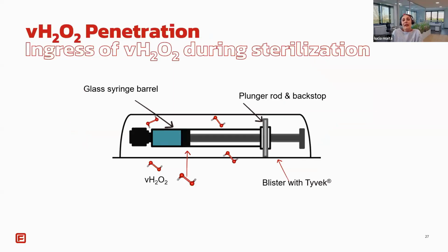This slide focuses on the key aspect of the H2O2 process: the sterilant penetration. The aim is to verify that H2O2 can effectively reach all the critical areas of the system, including the syringe barrel, the syringe component, the blister, and the Tyvek barrier. Understanding penetration behavior is essential because it directly affects the process robustness and reproducibility. In particular, we need to ensure that all the relevant surfaces are exposed to the H2O2, even in the presence of packaging constraints and complex geometry.